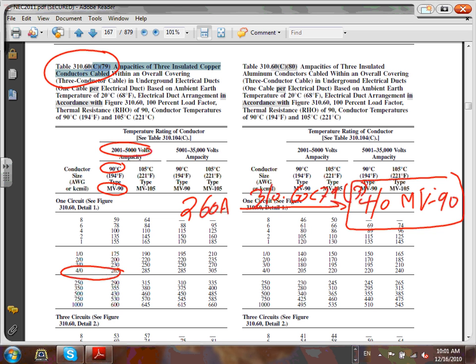Okay. Any question, guys, about this table? This is a new table that you're being introduced to for medium voltage cable. I want to bring your attention, guys, the smallest conductor you can use with this table is number 8. So if your calculation ends up with anything less than number 8, what are you going to do? Number 8. If you're using voltage 13.8, the smallest conductor you can use is what? Number 6. Okay? Any question, guys, about using this table?